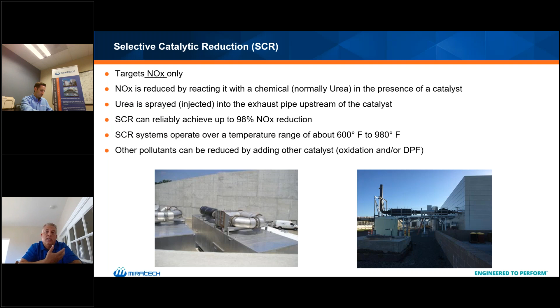These SCR systems have a pretty narrow range of operation, about 600 to 900 degrees Fahrenheit, but the good thing is almost all the IC engine work we do is right in that range, so it works very well. If you need to remove other pollutants, you can add those upstream before this system, and that builds up to what we commonly refer to as Tier 4 compliance systems.